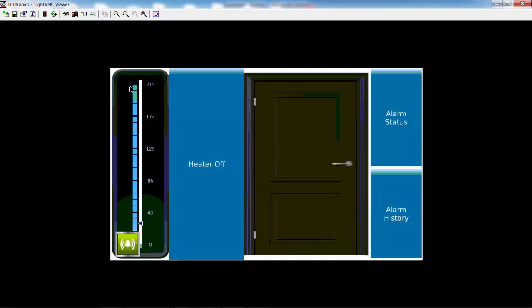Also on the alarm banner is a snooze button. This sets a time during which active alarms are not displayed in the scrolling window. When you press the snooze button, the banner minimizes to the small button mode. Note that this is only effective for an alarm that has not changed state. If an alarm that was inactive becomes active, it will be displayed even if the snooze is activated.